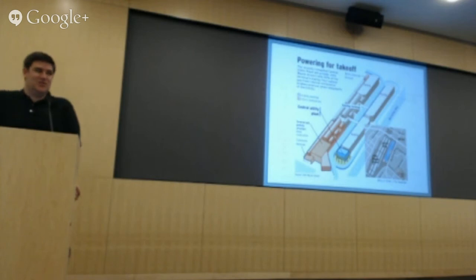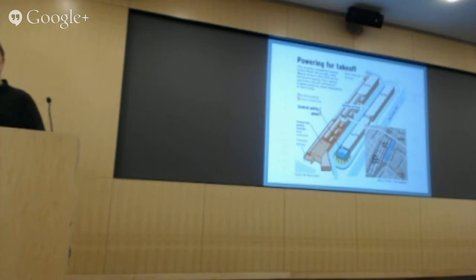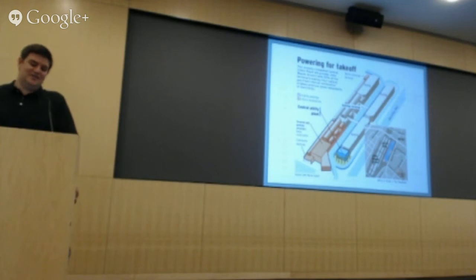And the problem was their switch yard to Southern California Edison was right there. And it was a large one because they actually took power at a higher voltage. As a commercial customer, the higher voltage you go, the cheaper it is because you own more of the equipment to bring it to you. So when you're reducing the size of your substation that they need, the cost went way up.